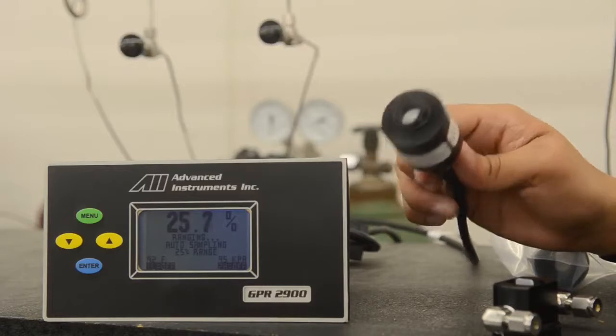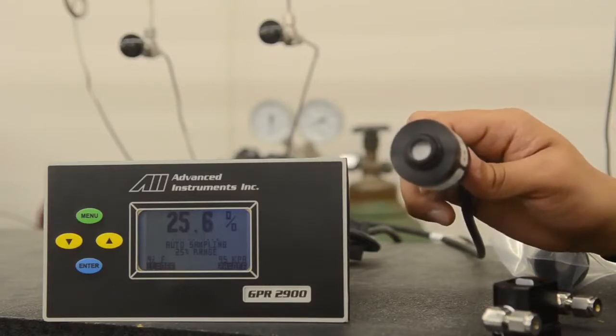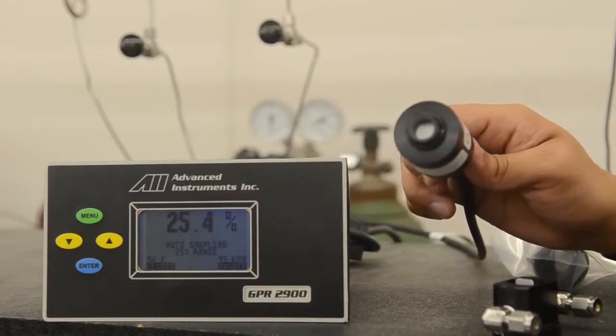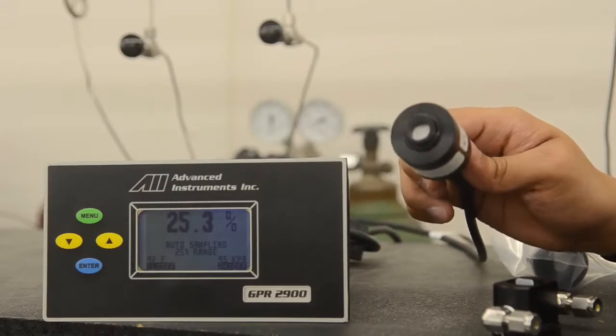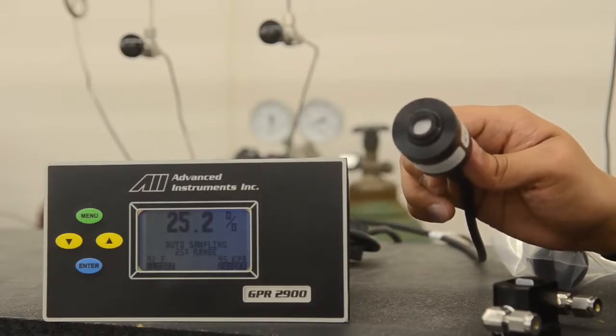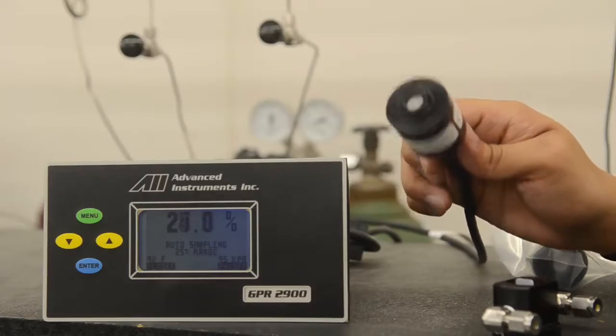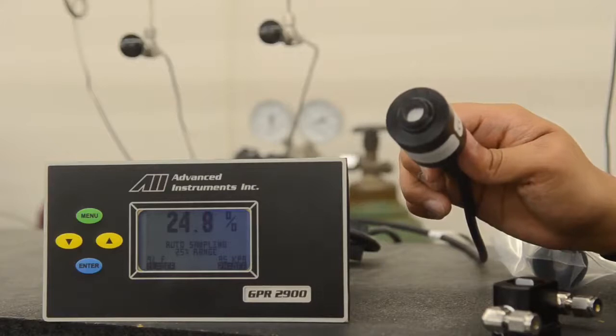What you want to do is confirm your connections are solid and you have a valid reading. No one sensor is produced the same and will have varying outputs. Thus, when you first install your sensor, you may not read 20.9. Do not be alarmed, as that's what the calibration is for. You just want a healthy sensor that will respond to oxygen, as we see here.